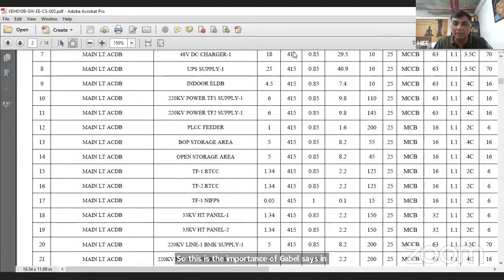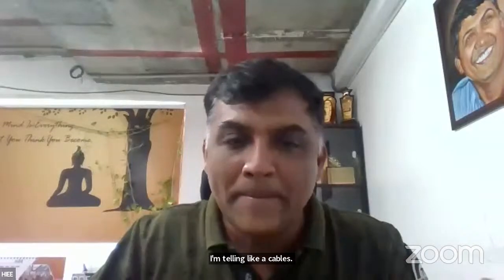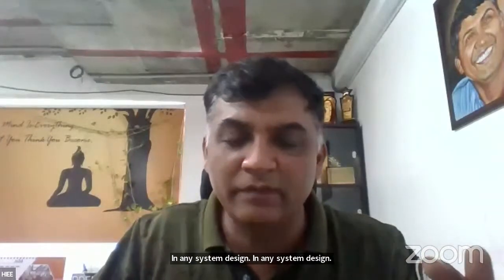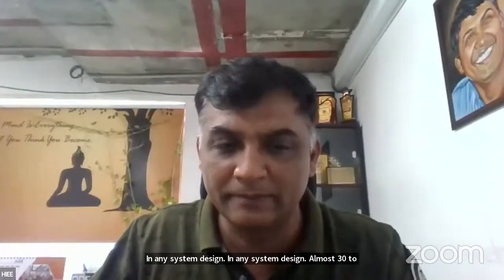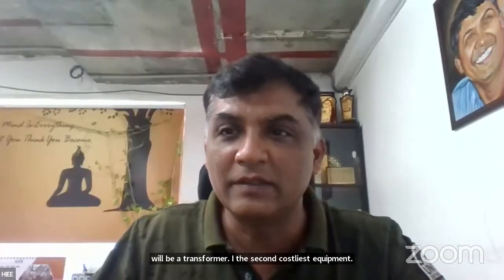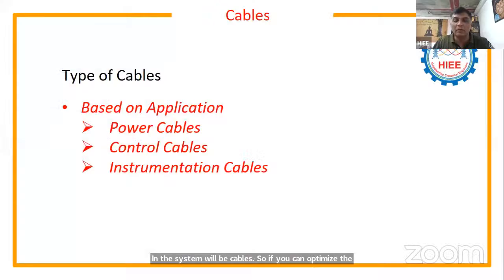Why I'm telling this is because in any system design, almost 30 to 35% of the system cost is borne by cables. The first and foremost costliest equipment in the system will be the transformer, and the second costliest equipment in the system will be cables. So if you can optimize the cables properly, then you can save a good amount of money and make your project economical. That is the most important equipment in the electrical system.